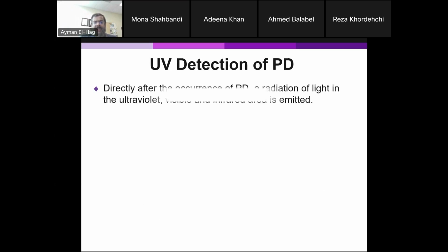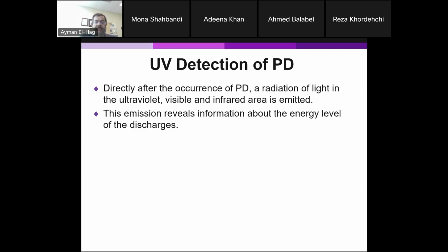UV detection of partial discharge. Now, as PD happens, as I mentioned, there will be a radiation of light in the UV range, in the visible range, and in the infrared. The most relevant spectrum for us at the PD level is the ultraviolet spectrum. This gives you some sort of feeling about the energy level, the intensity of the UV light. It gives you an indication about the level of the partial discharge, although that is of course a very relative perspective.